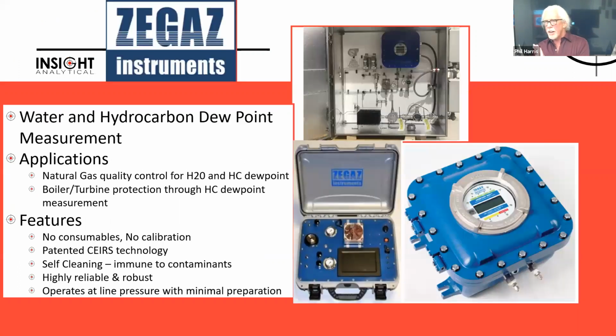On the natural gas side again, ZEGAZ is a chilled mirror type water and hydrocarbon dew point analyzer. So it can simultaneously do both the water dew point and the hydrocarbon dew point of a natural gas stream. It's not really a chilled mirror, but it's a chilled optical surface. It cools an optical surface as the gas is flowing over it. And when it hits the dew point, liquid starts to drop out on the surface. From the liquid's presence and using a spectroscopic technique, they can tell if that liquid is water or if it's hydrocarbons. So it allows us to do both of those dew points by the most accepted method for truly determining dew point, which is chilled mirror.